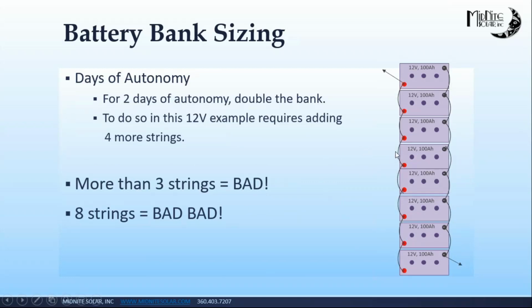I've had calls from people that have had 10 or 12 of these 12 volt batteries. What happens is, you put your positive here, your negative down here, and by the time the current flows down inside, the resistance impacts the voltage applied to these middle batteries, and they just don't charge as well as the others. A constantly undercharged battery sees a slight voltage drop, it weakens, and that weak battery pulls the whole bank down.